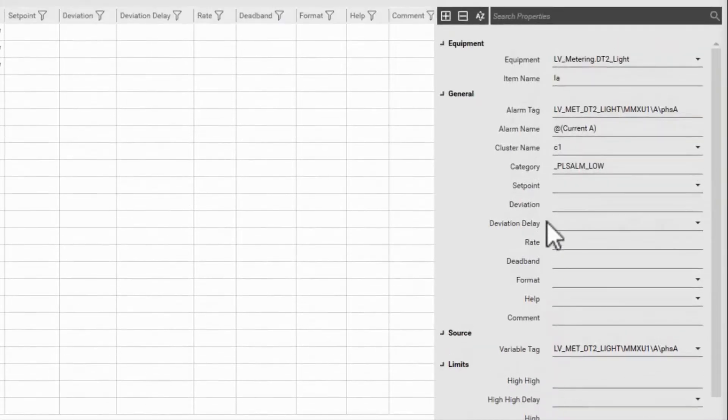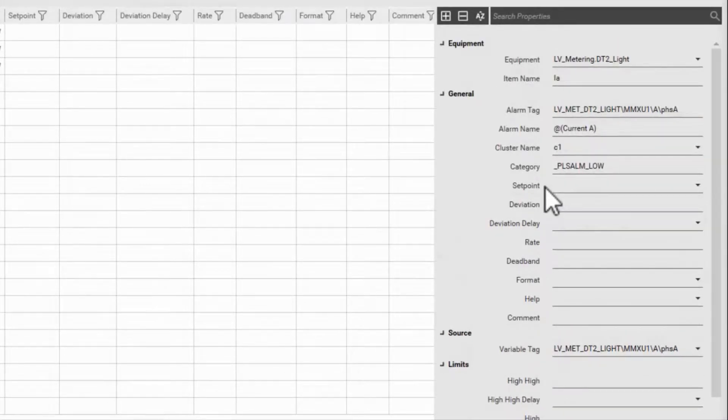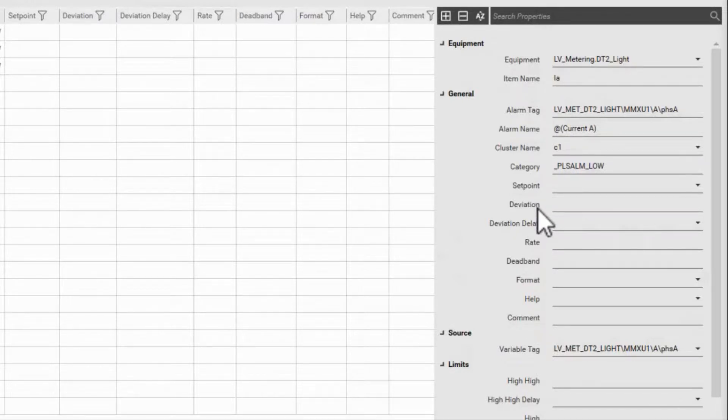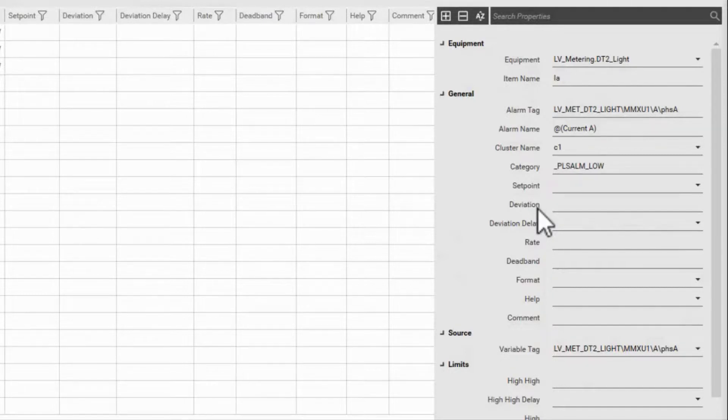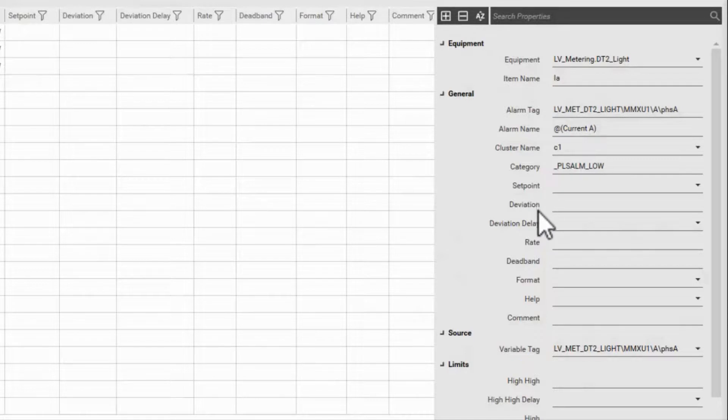...the set point field can be configured with a fixed value or a variable tag. This works with the deviation field in that when the absolute value of the variable tag minus the set point is greater than the deviation, an alarm will trigger.